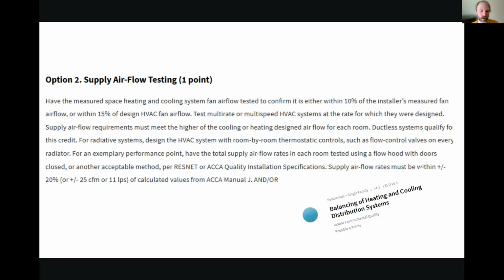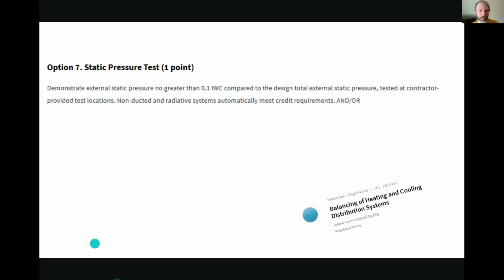There is no concern there. So you can use that pathway. Of course, when you do, that's going to be one of the components that leads to good static pressure, so it's not a drag on the health and performance of your system. And that might allow you to have a bigger MERV filter, which gets you more LEED points and has a healthier home.